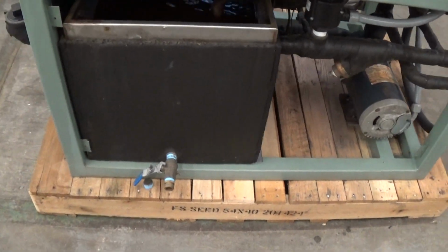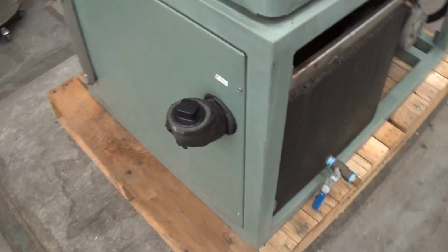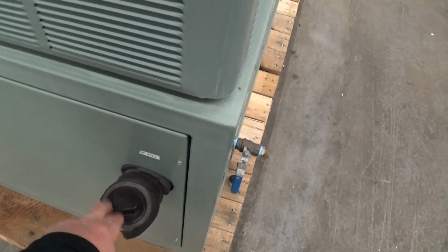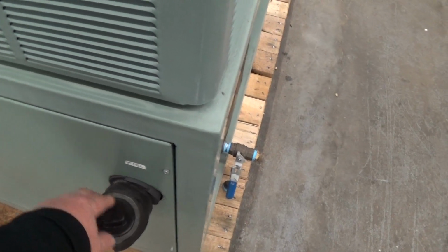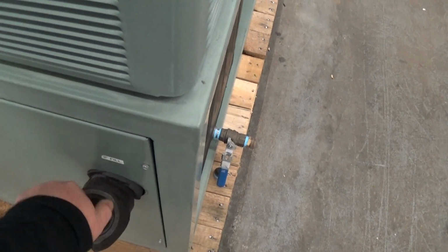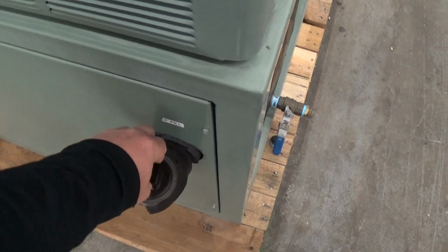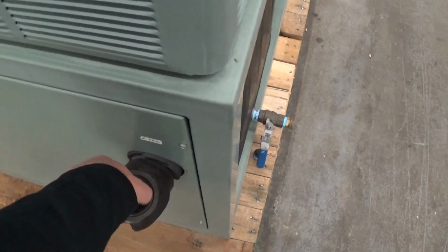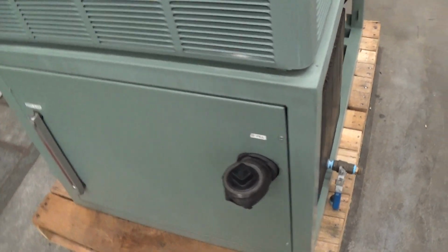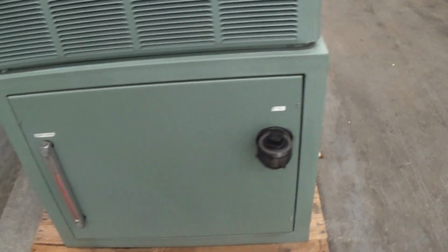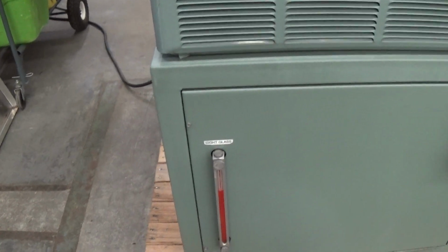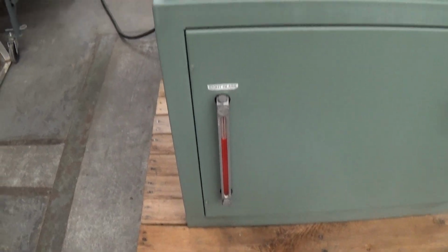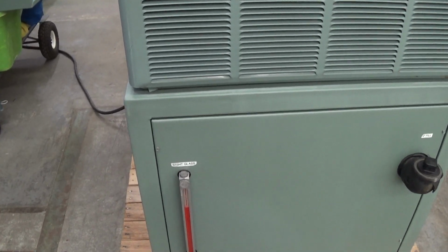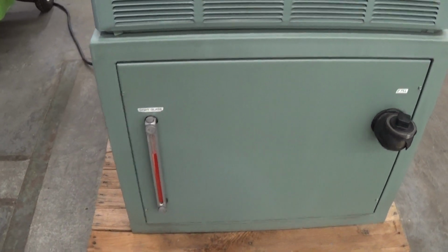There's your drain on your tank. Oh, this is kind of nice on these. This is a little fill port. Just open that up. It's 2 inches, and you can fill your glycol in there. So obviously you don't want to run the pump at all unless you have your glycol or water in there. We have a nice sight glass here on the tank.